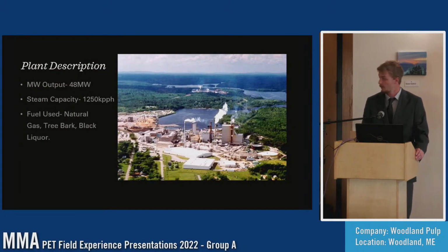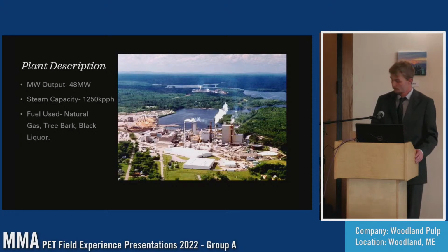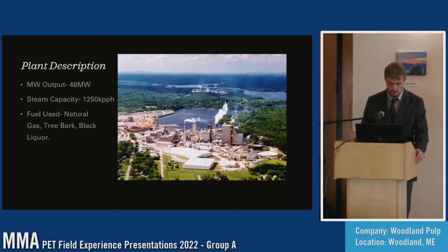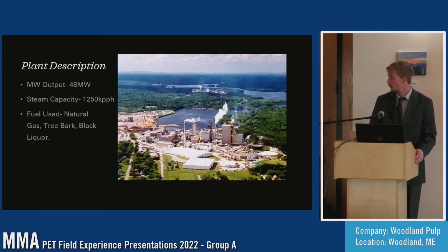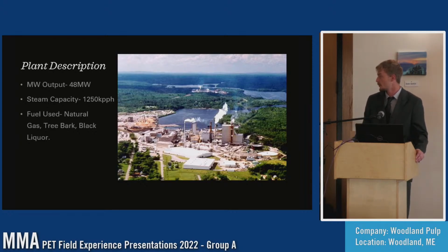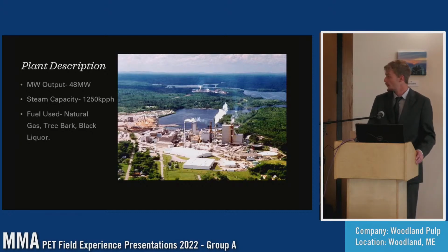Basic plant description: it outputs 48 megawatts, including the 10 hydro turbines that we have. 7 of them are at the on-site dam, and the other 3 are at an off-site location, Grand Falls. The other 40 megawatts is made up by 2 steam turbines. Turbine number 10, manufactured by GE, is a 23 megawatt average output, and number 11 is a 17 megawatt average output. Steam capacity is 1250 kilopounds per hour, made up by 2 boilers: the number 3 recovery boiler and the number 9 power boiler. Number 9 is the swing boiler, so that changes if we need any extra process steam or if the header level's dropping.